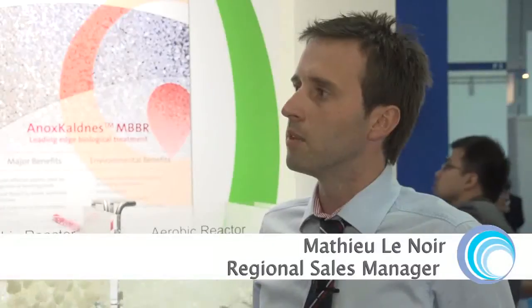I just want to introduce the Anitamox process. It's a process to treat the reject water, because the reject water is really rich in nitrogen and really poor in BOD. So we need to have a dedicated sidestream treatment when we use the Anitamox process, so we avoid having such a bad impact when we recycle back the sidestream directly to the mainstream, such as high energy consumption and higher sludge production.